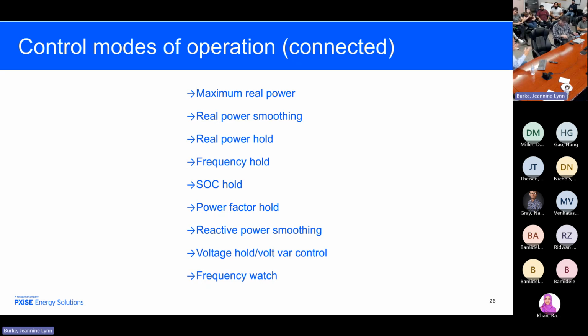If everybody has frequency watch on their microgrid, then when you get an event, it operates like a traditional droop control. It acts right now to inject or withhold real power. If it's over frequency, you do the same.